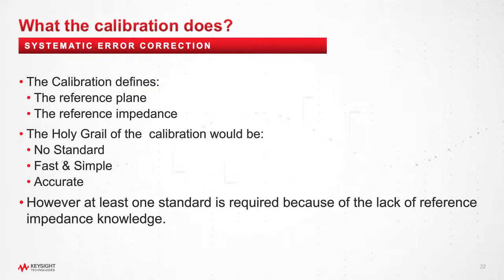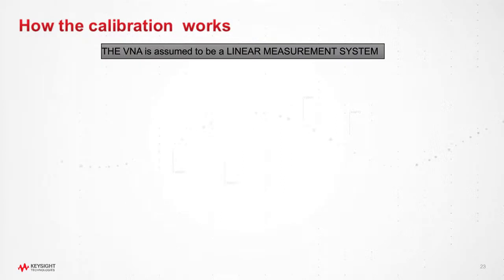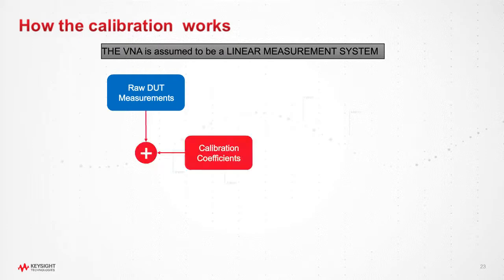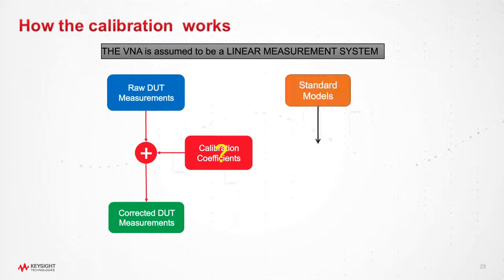So how does the calibration work? The VNA is assumed linear. So we start from some raw measurements. Then we plug in the error coefficients, the calibration coefficients, and we obtain the corrected measurement. Since the system is linear, this operation is a linear operation. How do we compute the error coefficients? Well, we have some standards which are given by some models, can be electromagnetic or can be mechanical with the electromagnetic analytical model. Then we do some standard measurements and we compute the calibration coefficients out of them.